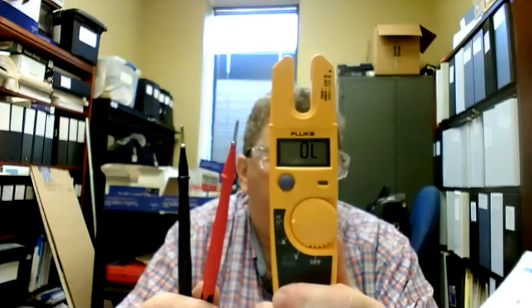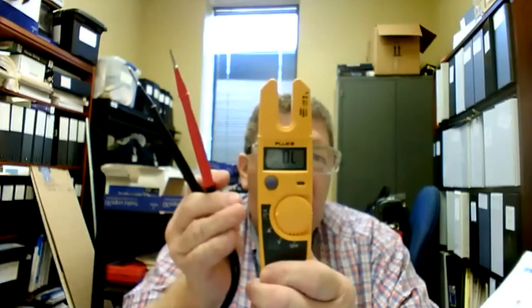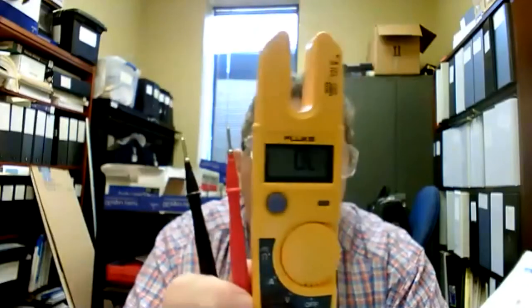And when we're measuring ohms, we're going to use the probes, okay? We use the probes to check voltage, and we use the probes to check ohms. By the way, when you're checking ohms, make sure you never put the probes on a circuit that's powered up. Because if you put it on ohms and touch a live circuit, you can damage the meter, you can damage the circuit, you can actually have it blow up in your face. It can be fatal. So here's why that is.